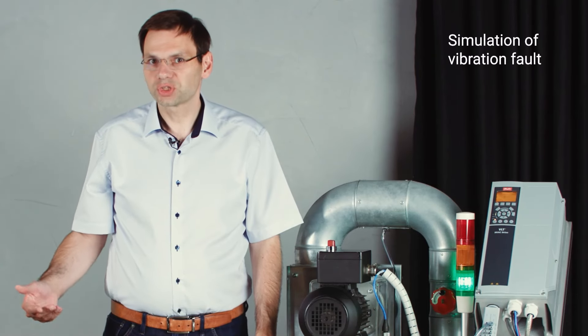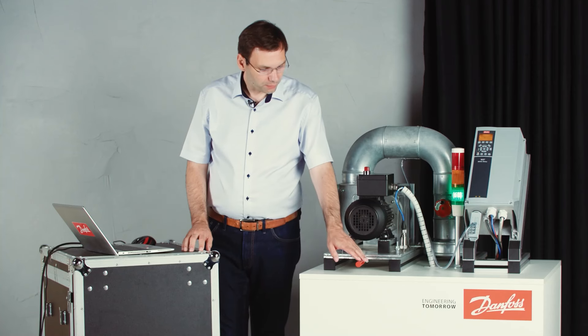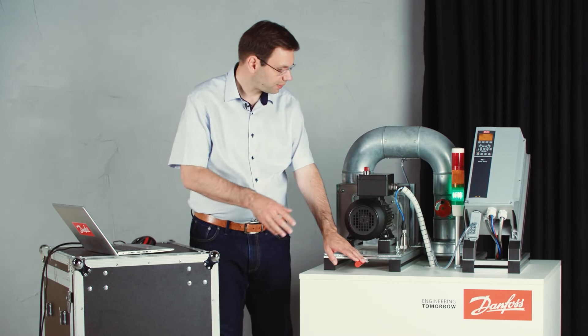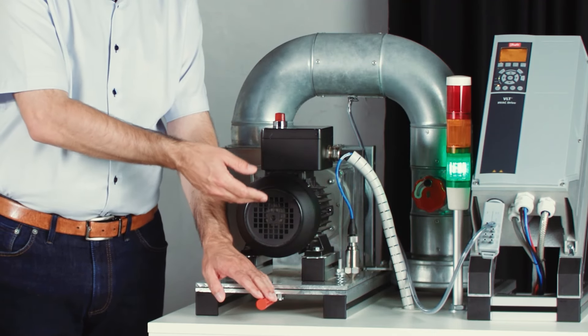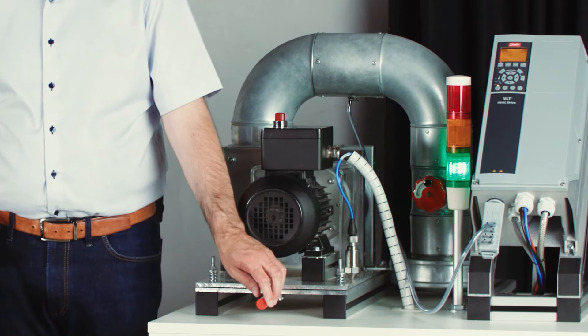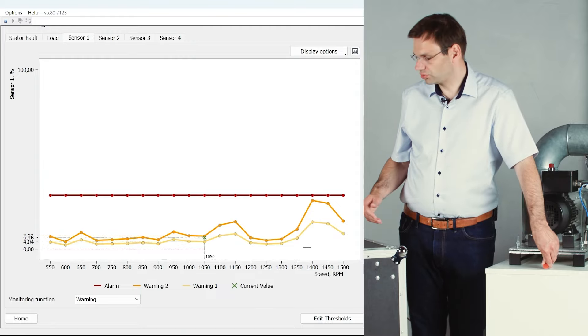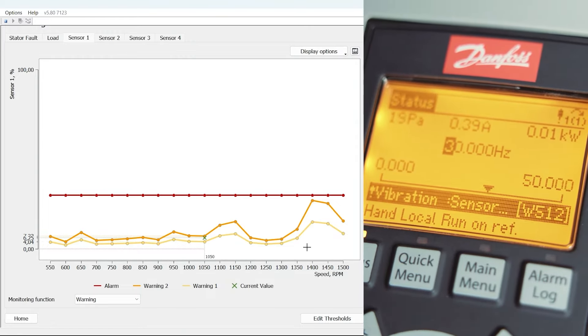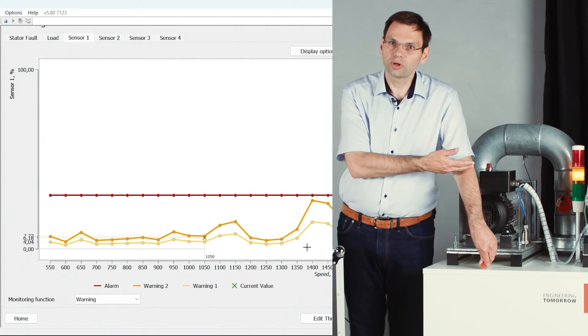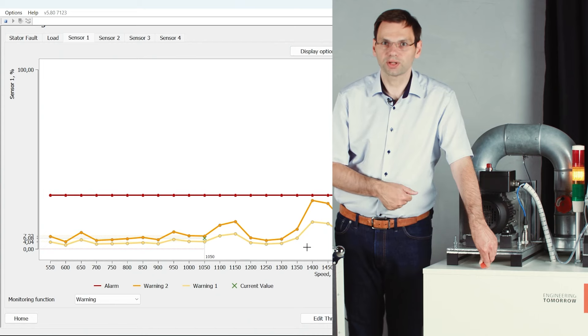The next fault is vibration monitoring. This is the only fault which requires an external sensor, connected to the analog input of the drive. I'm going to use the handle to create a misalignment between motor and fan, which will increase the vibration measured by the sensor. I push down the handle, misalignment is created, and you can see on the screen the vibration level increased. The yellow light turns on, giving a warning — also visible in the drive display.